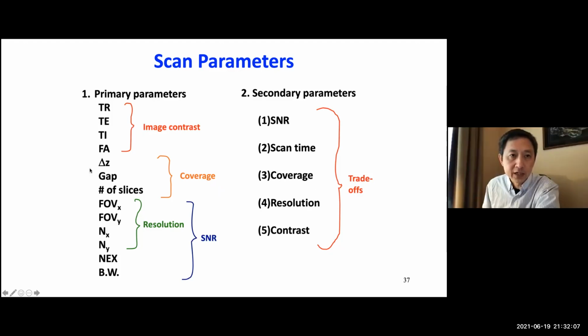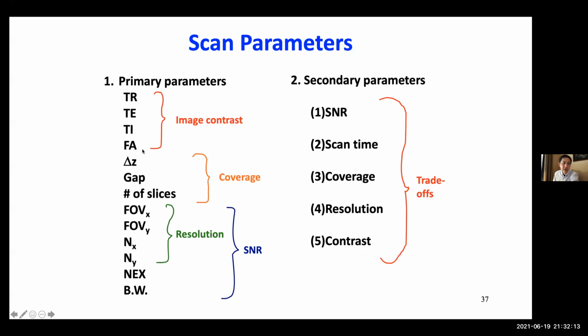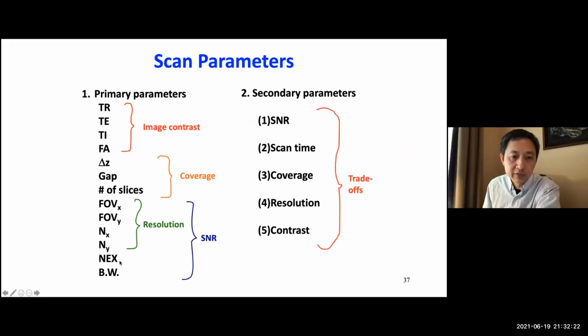So on the left-hand side are the primary parameters that can be manipulated by the operator: TR, TE, inversion time, flip angle, slice thickness, gap, number of slices, field of view in 2 directions, matrix size in 2 directions, number of averages, bandwidth. Those are on the MRI console and can be changed by the technologist. And then on the right-hand side are those related to image quality. Those are the results. We can call them secondary parameters, including SNR, resolution, contrast, but also scan time, which is very important for any scanner. Coverage is important. We want to make sure the lesions are covered.